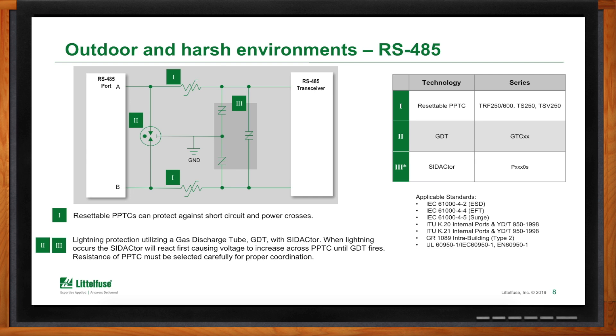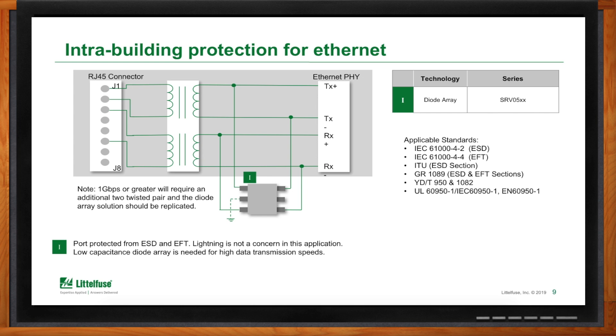For Ethernet intra-building protection, you can generally use a simple diode array such as the SRV series. This provides port protection from electrostatic discharge and electrical fast transients, and is suitable where lightning is not a concern. One advantage of this diode array is its low capacitance, which enables high transmission speeds. If you need data speeds greater than 1 gigabit per second, you'll require additional twisted pairs beyond the example shown.